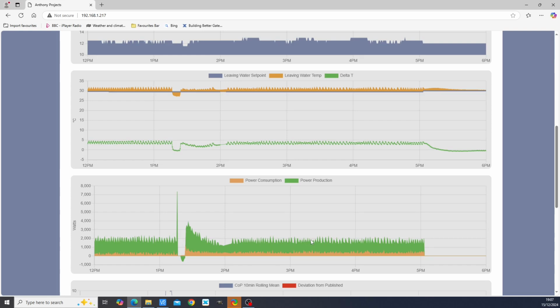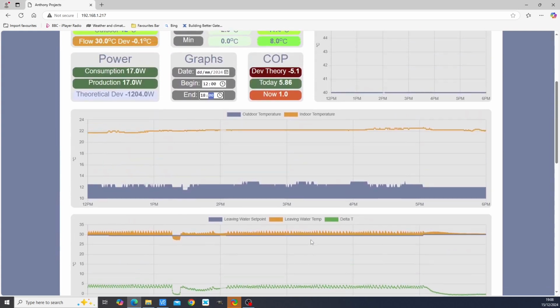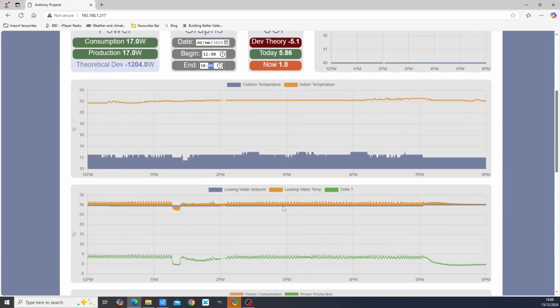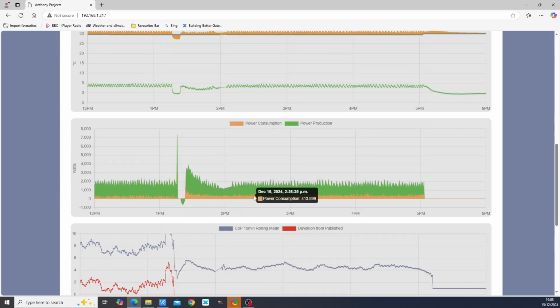So here's the thing, and this actually informs my opinion. For a given minimum output, as the ambient air temperature warms up, then the capacity to generate higher output increases. That's your improvement in coefficient of performance. But in order to accommodate that capacity, your radiator temperatures also have to increase with higher ambient air temperatures. You don't need the radiators to increase with higher ambient air temperatures, but to get that efficiency, you need to increase the flow temperatures. So in this instance, my conjecture is that if I increase the leaving water temperature from 30 to 35 degrees Celsius in this regime, then even at the minimum flow rate here, we would be able to get some much better, some spectacular outputs here.